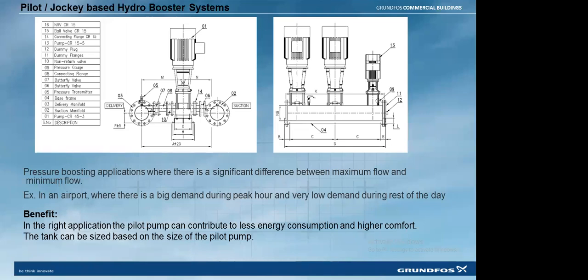When you have a very variable load on the system side, take an airport as an example. Only at peak time will you have maximum water consumption, when flights are landing or taking off and maximum people are utilizing the utility area. At other times it will have much lesser water consumption. It may come below 25% of your designed capacity. So whenever the flow rate goes below 25% of design capacity, we can have this pilot pump to take care of your minimum requirement.